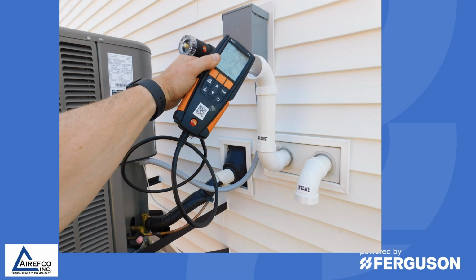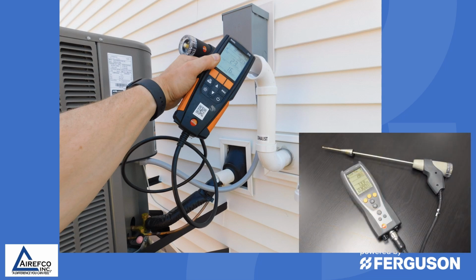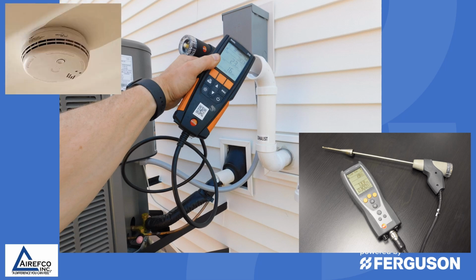If the exhaust is under 10 feet, you can probably take the CO reading at the termination point for the exhaust at the outside of the home. If it's over 10 feet, or 30 or 40 feet long, it is recommended that you drill a hole 12 inches from the inducer motor and insert your probe to take the reading. We also recommend highly in these videos that any home that has a gas appliance installed in it should have a carbon monoxide sensor installed.